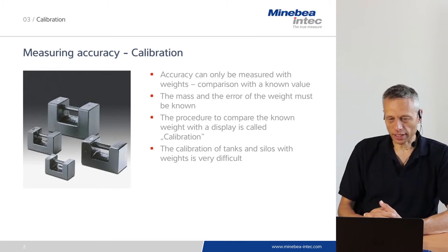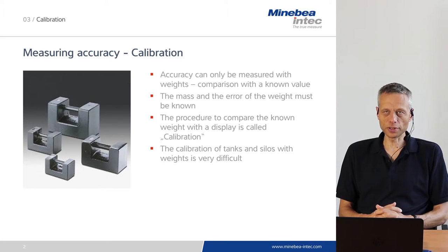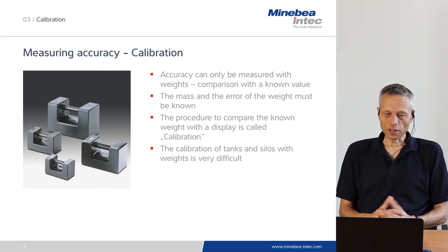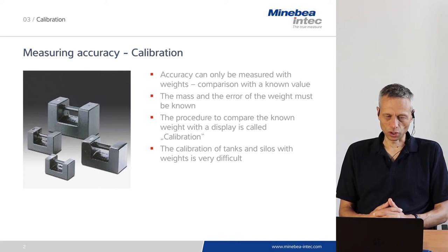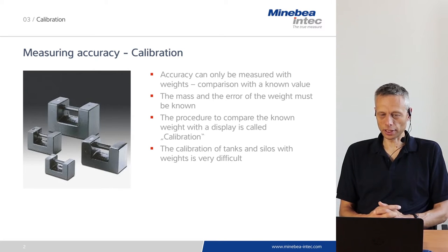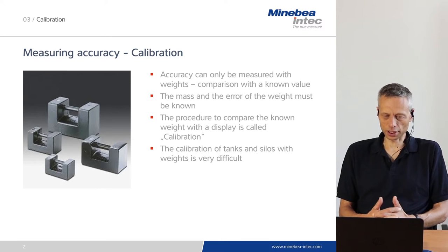Accuracy of a process vessel scale can only be measured with weights. That means a known weight has to be compared with the display readout, and possible differences need to be corrected. The mass and the error of the calibration weight must be known. This is a reference weight, and the procedure to compare the known weight with the display is called calibration. We also make a difference between just the readout and the correction of the difference, which is called adjustment if we correct the difference.